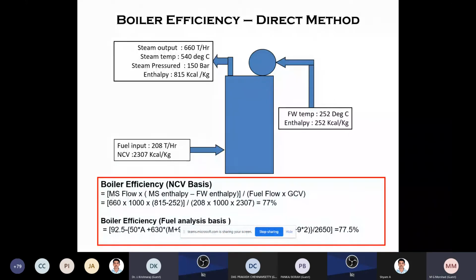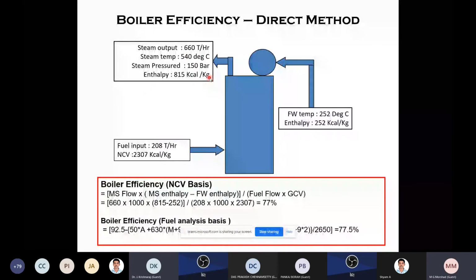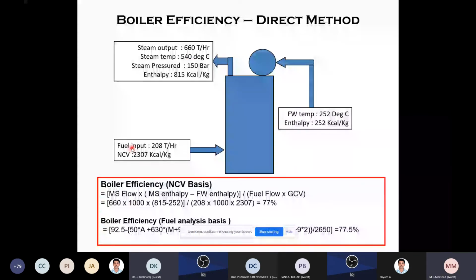Okay. So boiler efficiency. You can measure the efficiency of the boiler by two methods: one is the direct method, another is the indirect method. In the direct method, you only get the efficiency, and in the indirect method, you get the losses and the reasons for the losses. At any time, if you enter the power plant control room, you can get all the data from there. Steam output, what is coming out from the boiler: steam flow, steam temperature, steam pressure, and from these data you can get the enthalpy from the Mollier chart, or nowadays software is available. This is coming out from the boiler. What is going inside the boiler? The fuel, in tons per hour, and the GCV.